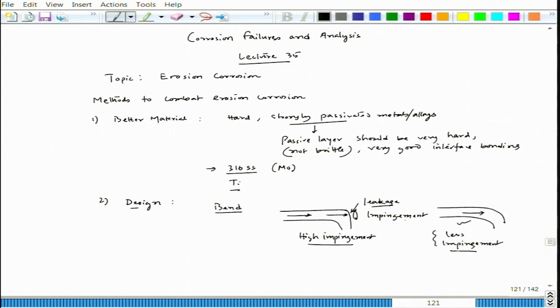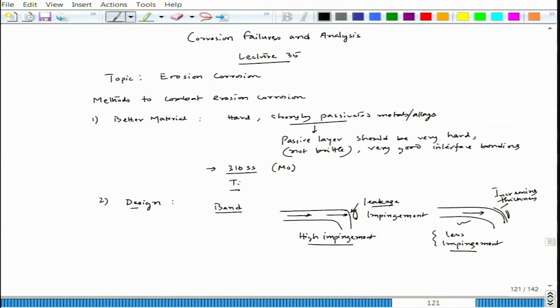Since we cannot reduce impingement completely, there will still be impingement and erosion corrosion at that location. One possibility is to think of increasing the thickness there so that it can last for a longer period. This is one sort of design.